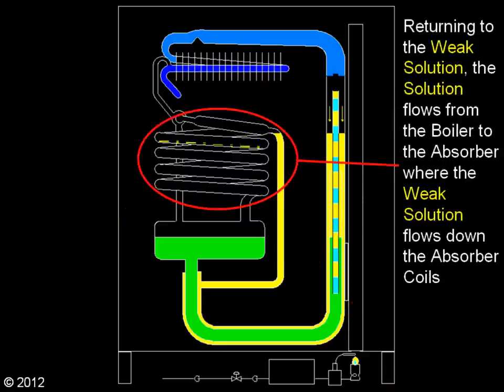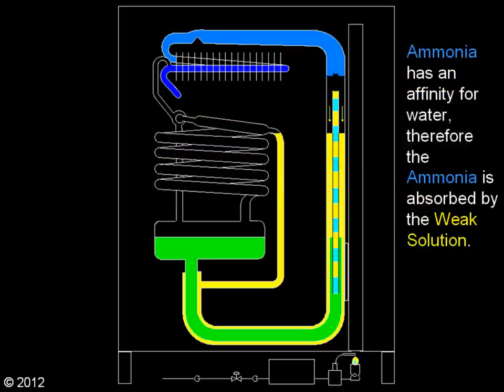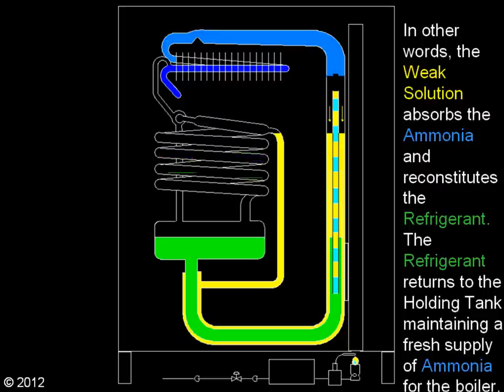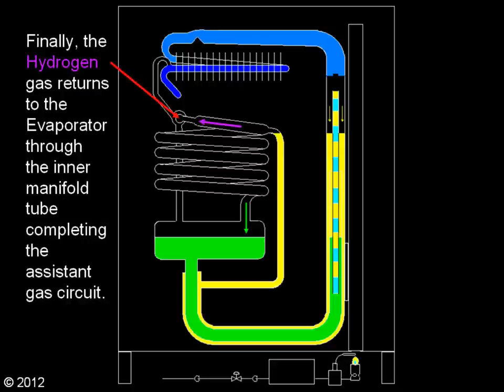Returning to the weak solution: the solution flows from the boiler to the absorber, where the weak solution flows down the absorber coils. Ammonia has an affinity for water; therefore, the ammonia is absorbed by the weak solution. In other words, the weak solution absorbs the ammonia and reconstitutes the refrigerant. The refrigerant returns to the holding tank, maintaining a fresh supply of ammonia for the boiler. Finally, the hydrogen gas returns to the evaporator through the inner manifold tube, completing the assistant gas circuit.